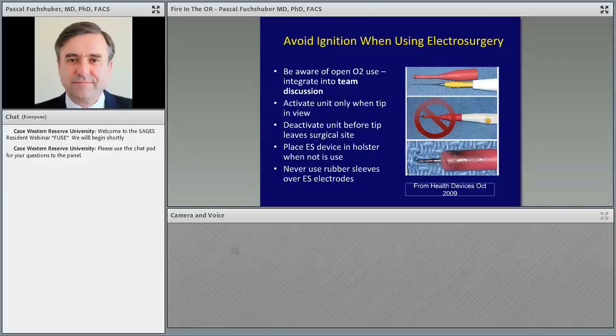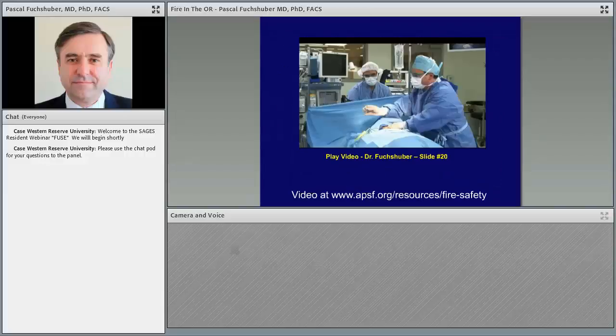When you have a monopolar device, wait till you can see where the tip is before you activate it. That's especially important in laparoscopic cases. Make sure the tip touches the tissue so you don't have arcing, which is a perfect way to start a fire, and deactivate the unit before the tip leaves the surgical site. Place the electrosurgical device in a holster, so don't place it on the field somewhere. It will burn through the drapes. And as shown on the picture here, and I don't know if anybody still does that, but if you see somebody doing that, please don't learn that that's a good thing to do. It's not. Don't use any of these rubber sleeves.